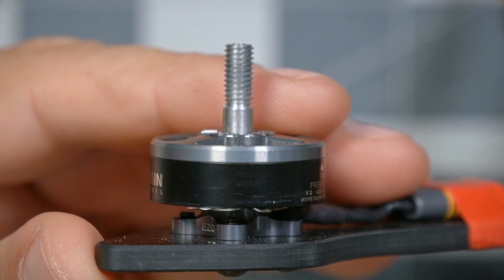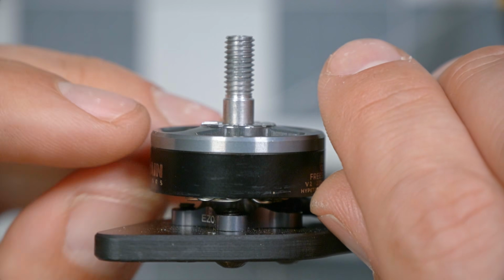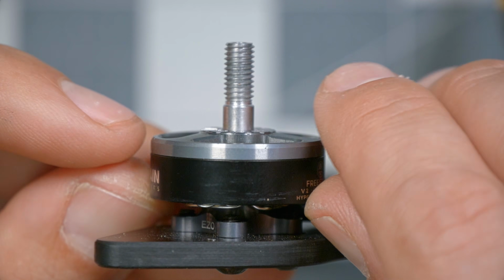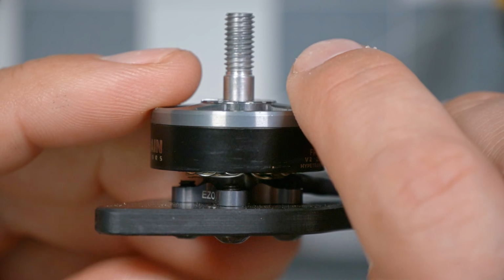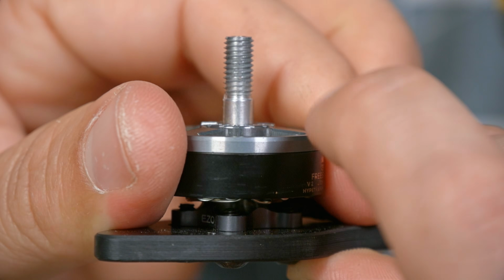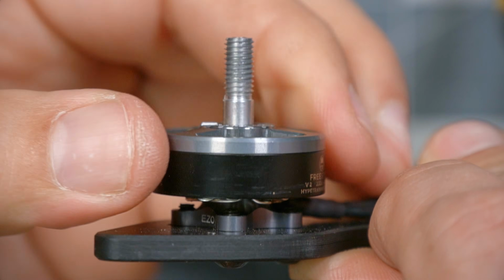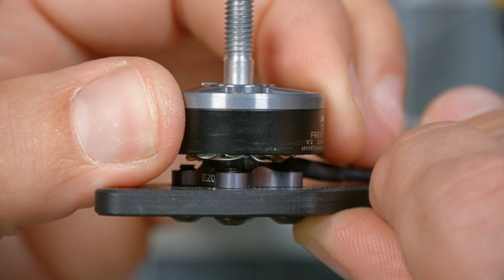The other mechanical check I like to do on a motor is to check for vertical play. I'm going to push or pull up and down on the motor and feel how much vertical play there is in the shaft. This motor has literally none—you can't see and I can't feel any movement. There could be as much as maybe 0.5 millimeter of vertical play.